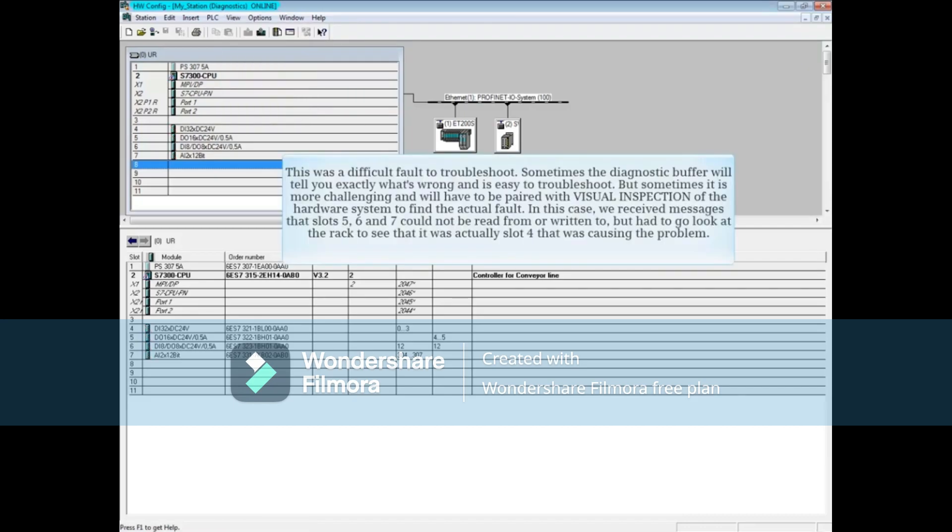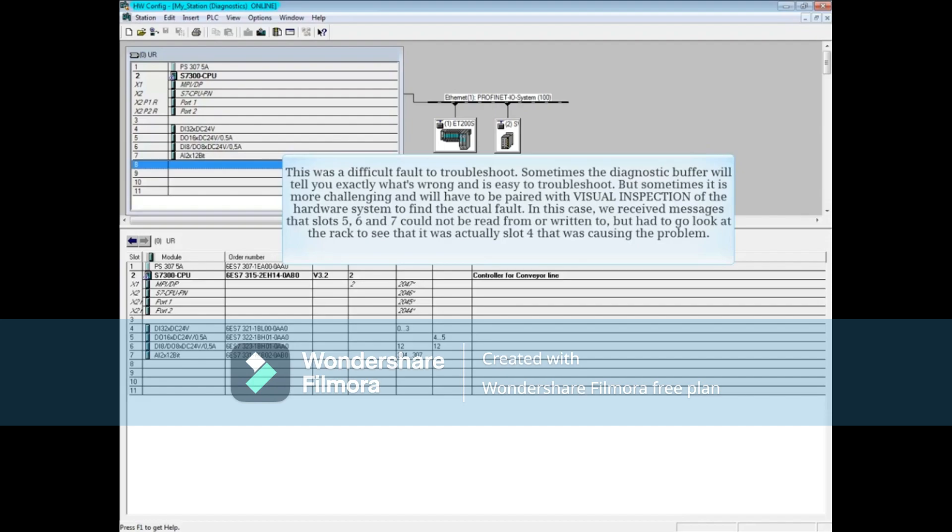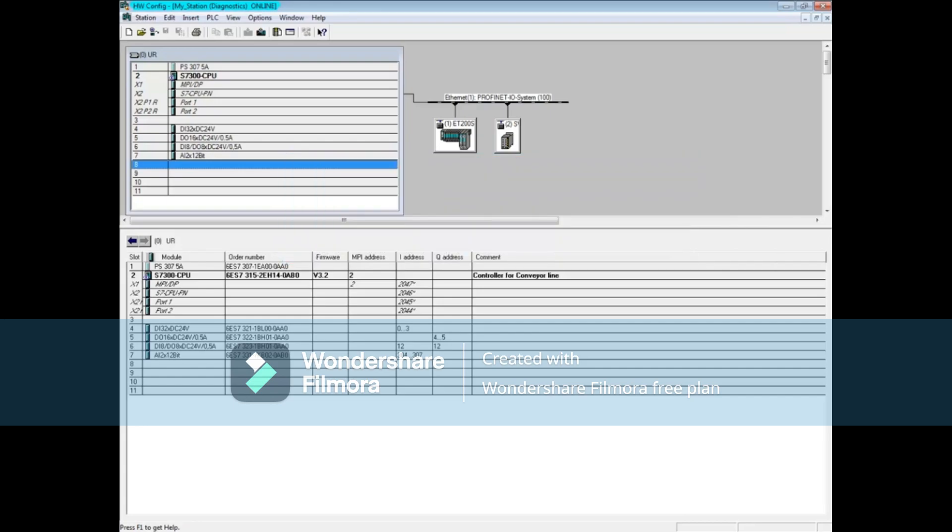This was a difficult fault to troubleshoot. Sometimes the diagnostic buffer will tell you exactly what's wrong and is easy to troubleshoot, but sometimes it's more challenging and will have to be paired with visual inspection of the hardware system to find the actual fault. In this case, we received messages that slots 5, 6, and 7 could not be read from or written to, but had to go look at the rack to see that it was actually slot 4 that was causing the problem.